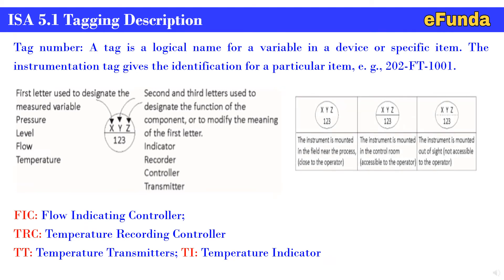Similarly, one can see another table where we have indicated three items. First item X, Y, Z, 1, 2, 3 indicated in a circle - the instrument is mounted in the field near the process, close to the operator. Second, with a circle with a centerline - the instrument is mounted in a control room accessible to the operator. Third figure, one can see a circle with a dotted line at the center - the instrument is mounted out of sight, not accessible to the operator.